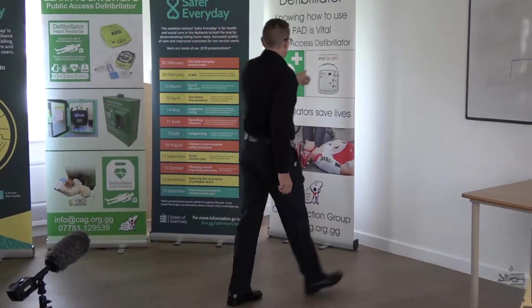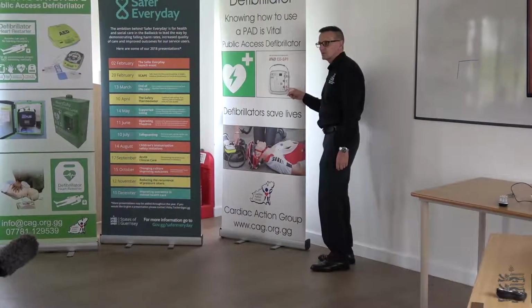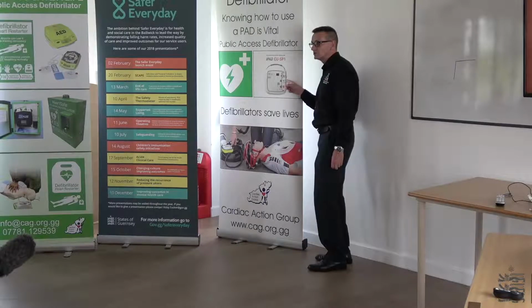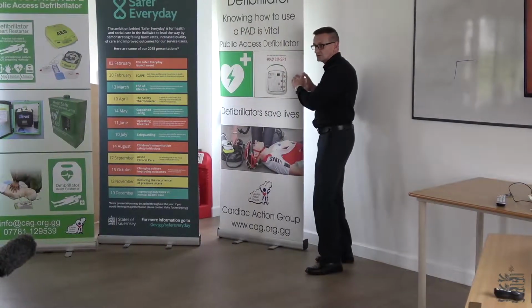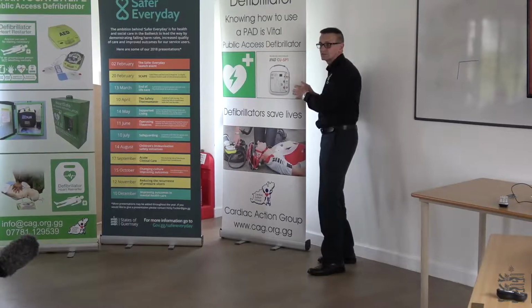If you have a defibrillator that's charged and there's an off button there and a shock button there, which button do you think a member of the public is likely to press? And it won't say, are you sure you want to turn it off? It switches off, and then you've got to wait another minute or so for it to switch on, check itself, analyse the patient, decide whether they need a shock, and then they can press the right button.